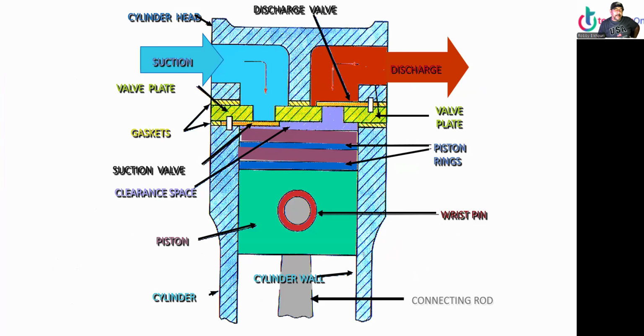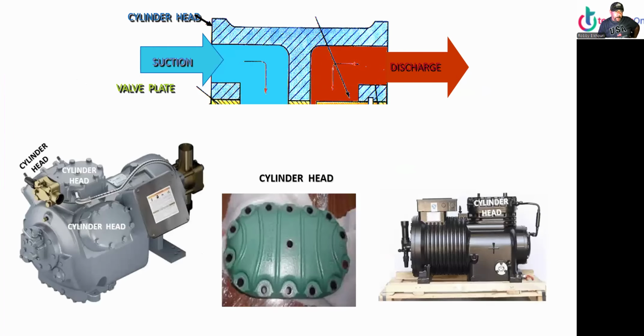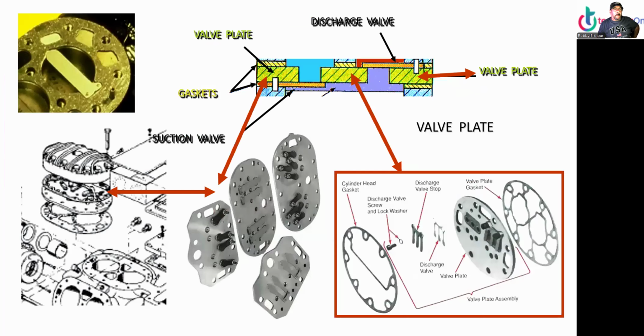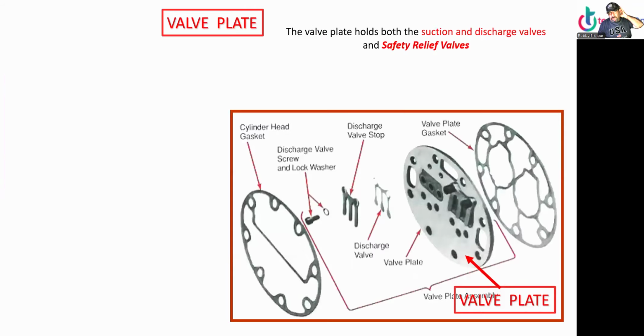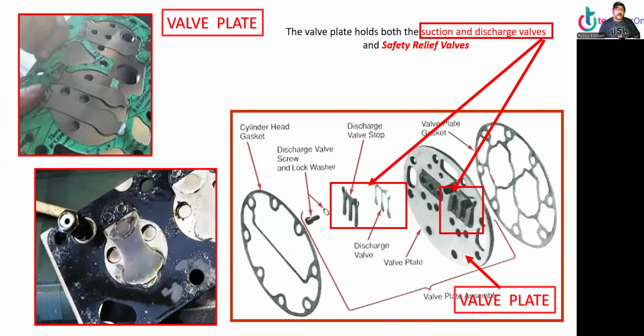I mean, the cylinder head. All right. So on top, this is the cylinder head, cylinder head, cylinder head. And this is the valve plate, valve plate, valve plate. You can see it there, all these valve plates. Cool. Now, valve plate. The valve plate holds both the suction and discharge valves and safety relief valves. So there's the suction and discharge valves there. And we have suction valve and discharge valve.